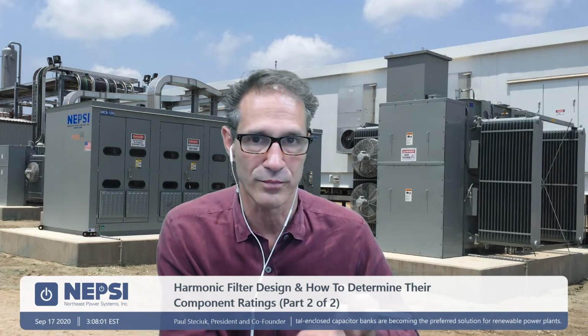So we then take an instrument, an SFRA instrument, which is typically used for testing transformers. We're going to hook that to the equipment, and we're going to get a sweep, an impedance curve, basically, of that harmonic filter system. It helps to verify that we designed the harmonic filter correctly, that it matches the impedance characteristics based upon the harmonic study, and then it helps to confirm that it's manufactured correctly.